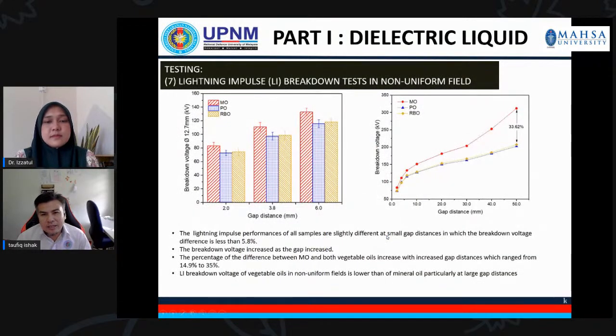And under the non-uniform field, we can see a similar pattern, in which the mineral oil has the highest breakdown voltage, followed by the rice bran oil and also the palm oil at different gap distances. What is interesting here is the lightning impulse performance of the oil samples. You can see from the curve here that the difference is slight at a small gap distance. However, the difference becomes larger as the gap distance increases, going up to 33.62% larger as compared to the smaller gap.